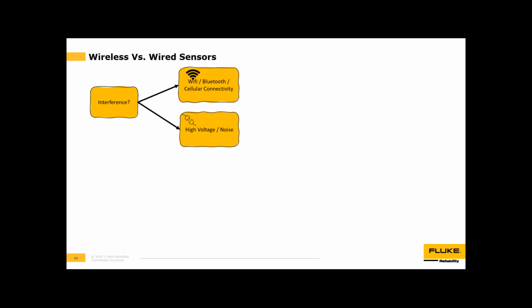But interference isn't only a wireless problem. If you're running a solid cable and sensor, it's possible to have high voltage interference depending on where you run the cable, or noise from something like a VFD or other machinery affecting the cable connection. So interference is an issue for both technologies.